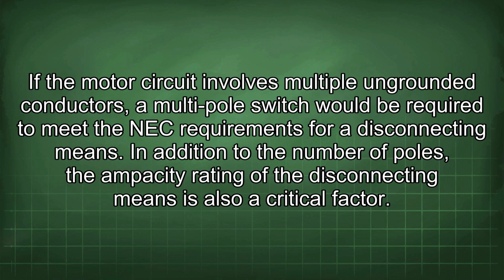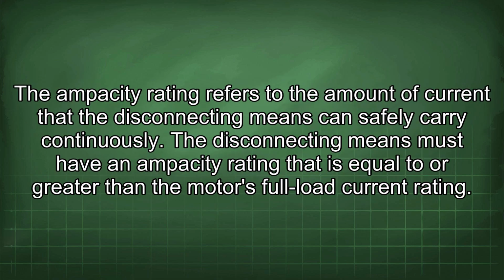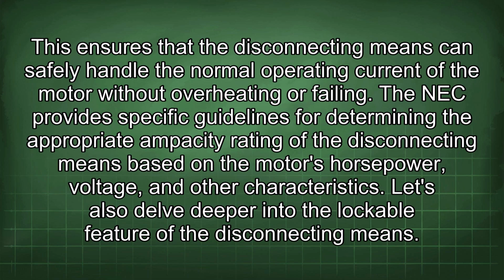a disconnecting means. In addition to the number of poles, the ampacity rating of the disconnecting means is also a critical factor. The ampacity rating refers to the amount of current that the disconnecting means can safely carry continuously. The disconnecting means must have an ampacity rating that is equal to or greater than the motor's full load current rating. This ensures that the disconnecting means can safely handle the normal operating current of the motor without overheating or failing. The NEC provides specific guidelines for determining the appropriate ampacity rating of the disconnecting means based on the motor's horsepower, voltage, and other characteristics.